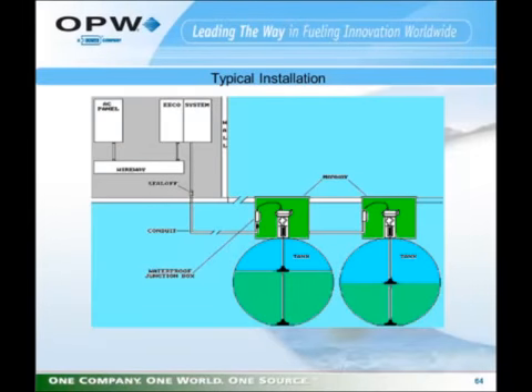Just the fact that we have two tanks, we have two probes in the tanks. The probes are connected to low voltage conduits that come into the building and into, in this case, the illustration is for an EECO 2000, the left hand portion being the high voltage and the right hand portion being the low voltage section. Note that the junction box at the tank is labeled as a waterproof junction box because the probe circuits are intrinsically safe. Explosion-proof fittings are not required at the tank, just weatherproof or waterproof fittings.